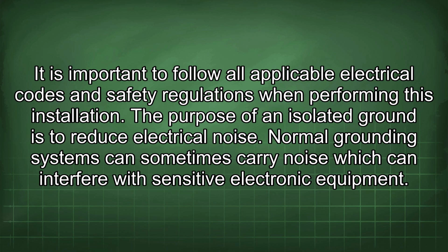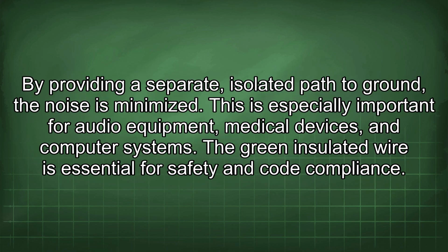The purpose of an isolated ground is to reduce electrical noise. Normal grounding systems can sometimes carry noise which can interfere with sensitive electronic equipment. By providing a separate, isolated path to ground, the noise is minimized. This is especially important for audio equipment, medical devices, and computer systems.